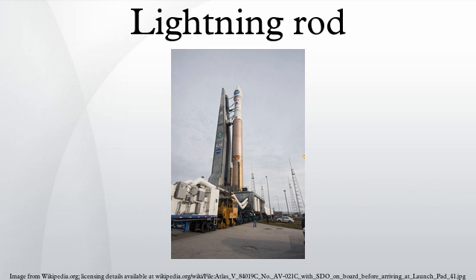A weak point in most lightning diversion systems is in transporting the captured discharge from the lightning rod to the ground, though. Lightning rods are typically installed around the perimeter of flat roofs, or along the peaks of sloped roofs at intervals of 6.1 m or 7.6 m, depending on the height of the rod. When a flat roof has dimensions greater than 15 m by 15 m, additional air terminals will be installed in the middle of the roof at intervals of 15 m or less in a rectangular grid pattern.